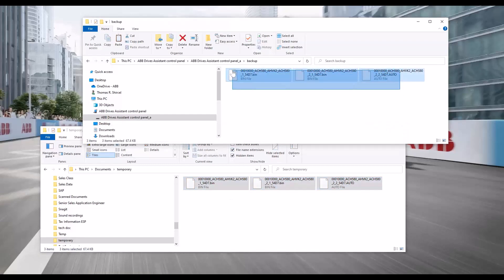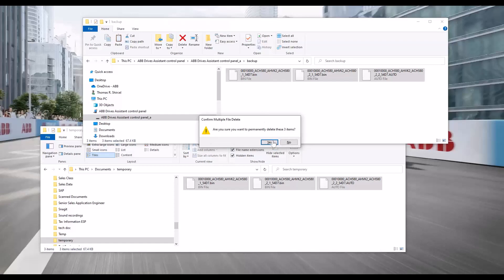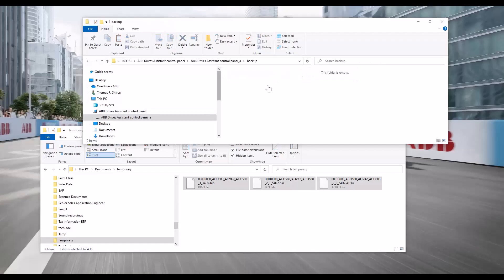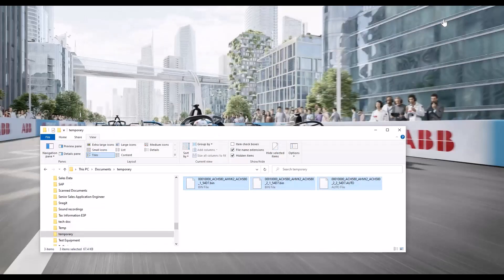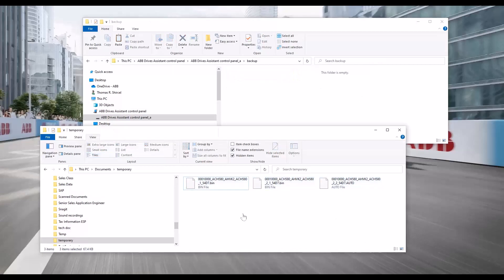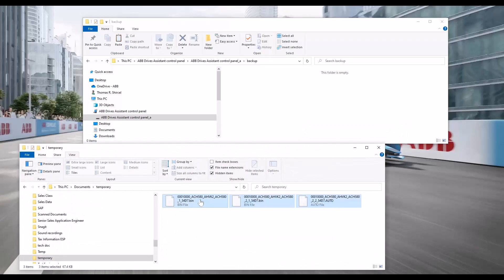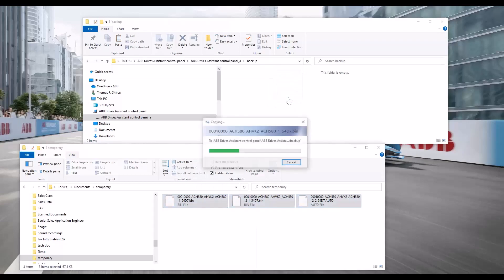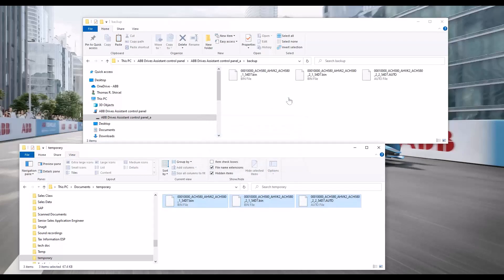I can go back into the keypad or control panel and delete the files — I've deleted them now. At this point the files are no longer there. So I can go look — the files are no longer in the control panel. Let's say I plug in a different control panel for a different drive. I can go on my computer, take the files loaded there, copy them, and move them straight over into the control panel — just like you would move something onto a USB device. Now the backup files are in the locations on the control panel and can be plugged onto another drive. You cannot change the name of the backup file — the backup file names cannot be changed. Therefore, when you store them on your computer, use a location or naming system for your folders, because if you change the name in any way, the file will not work.